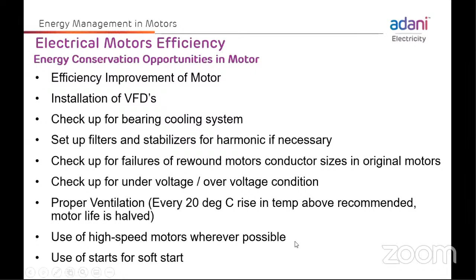Now you can see here these are some opportunities for energy conservation in motors. Efficiency improvement - we've seen VFDs installed in some places. Check the bearing cooling system, set up a filter stabilizer for voltage purposes, avoid failure rewinding of motors, check for under-voltage conditions of equipment, use high speed motors whenever possible, and use a soft starter for the system if possible.